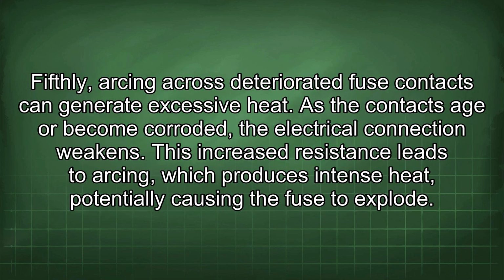Fifthly, arcing across deteriorated fuse contacts can generate excessive heat. As the contacts age or become corroded, the electrical connection weakens. This increased resistance leads to arcing, which produces intense heat, potentially causing the fuse to explode.